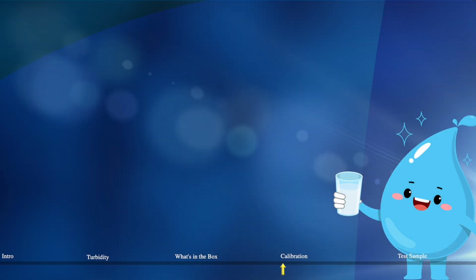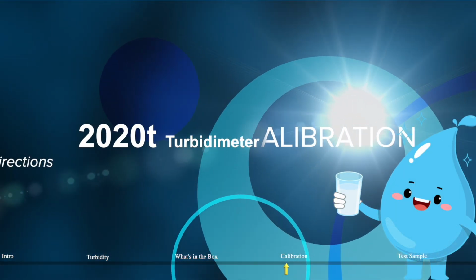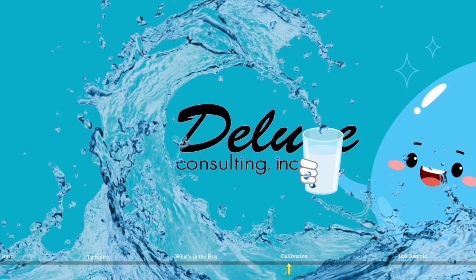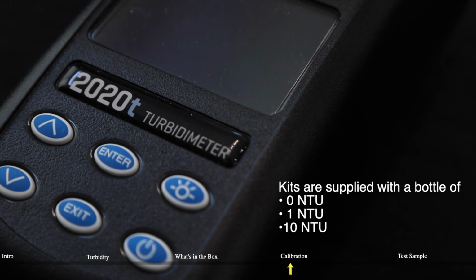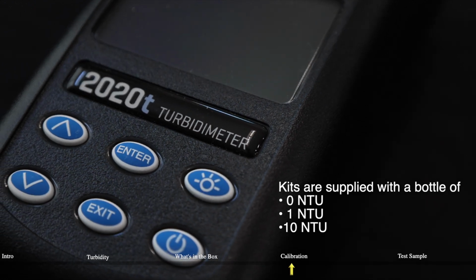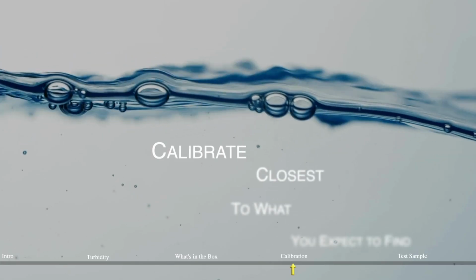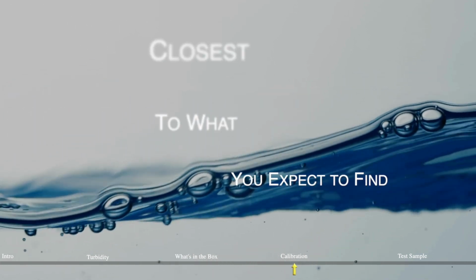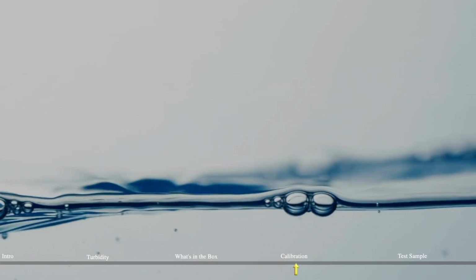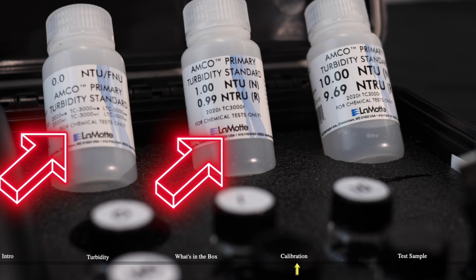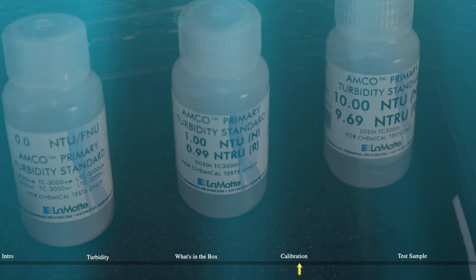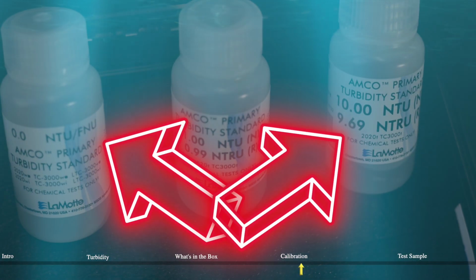Now, to give the proper reading for the clients, we are first going to have to calibrate our meter. This should be done each day before collecting any samples. For this meter, you will calibrate it for one of the 2 different readings you expect to get. If you expect to get a reading of 1 NTU or lower, then you need to calibrate for that by using the blank and the standard 1 NTU. If you expect to get higher readings, then you'll want to use the blank and the standard 10 NTU.